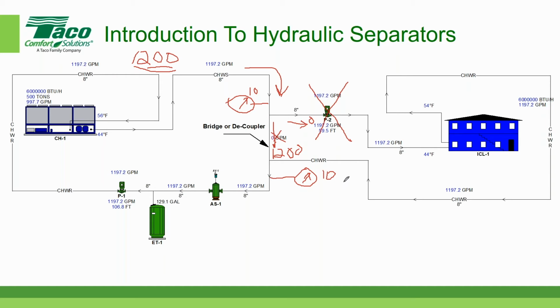Okay, so the pressure in both cases, as the water is flowing across here, is reading the same, which means that the pressure drop from this connection over here to this connection over here, for all practical purposes, is negligible, or pretty close to zero. So if we put a pressure gauge here versus here, not accounting for elevation change, assuming this section of pipe is all at the same elevation, the pressure should be reading the same value, and the pressure differential should be zero or pretty close to zero. So Brett, that's an important concept.